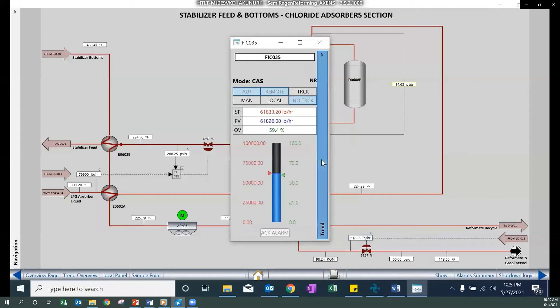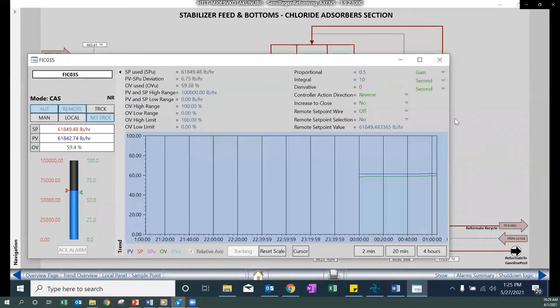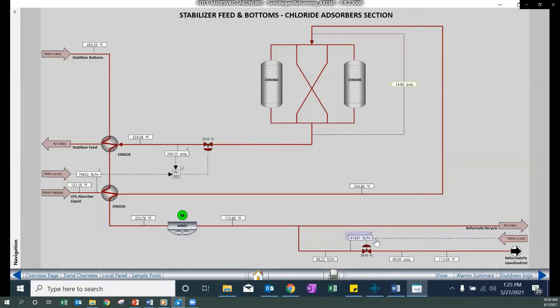So the reformate flow rate will be adjusted so that the level in the column will be maintained at the set point. So if we look at the reformate flow rate, we should see that it's increasing, but eventually it will start being controlled by the LIC, the level control, on the stabilizer column.